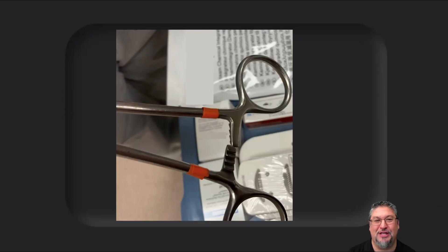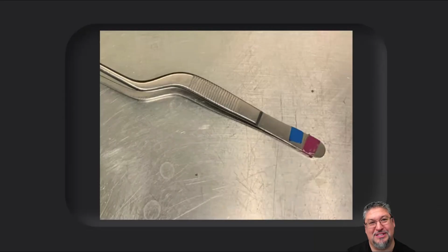Here are some pictures of instrument tape and some issues. You can see there's overlap or gaps, and anywhere we have gaps in the tape or pieces missing, that's a place where microorganisms can get in, and they're going to love being in that dark environment inside where that adhesive is. So make sure that it's just going 1.5 times around and that it's nice and cleanly sealed off. Here's another one where you can see it's starting to crack. It's discolored. It's having issues. Same thing here, where it's actually peeling up and you can see the areas peeling.